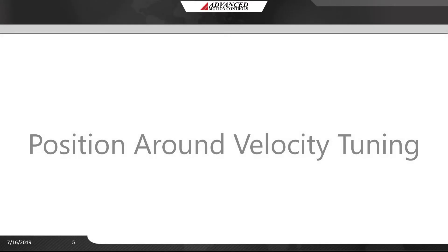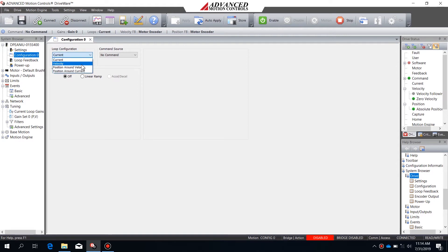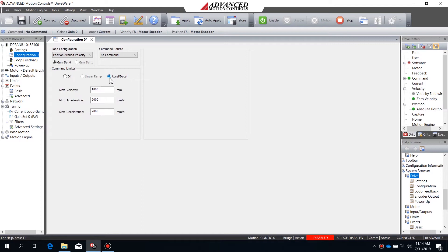The first methodology for tuning is position around velocity tuning. The first step in configuring position around velocity mode is to set up configuration zero. I'll change the loop configuration to position around velocity mode and then set up the command limiter for my system's max velocity, max acceleration, and max deceleration.